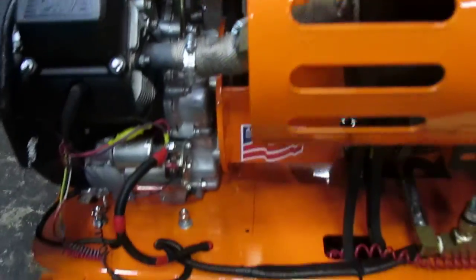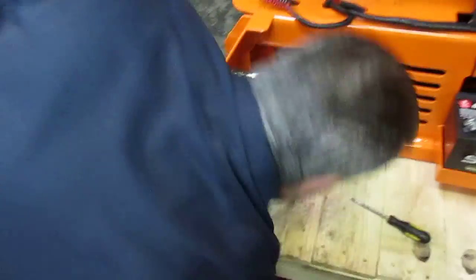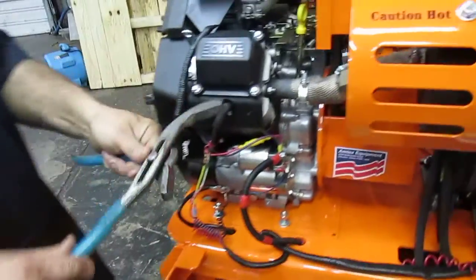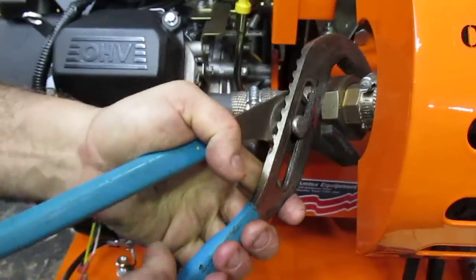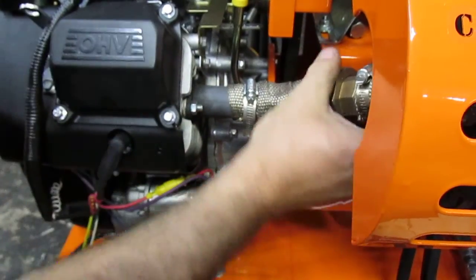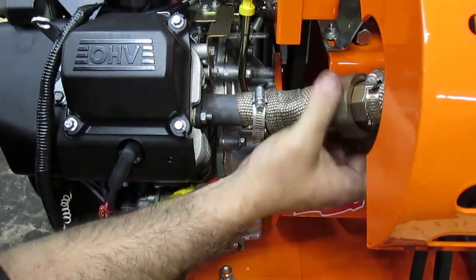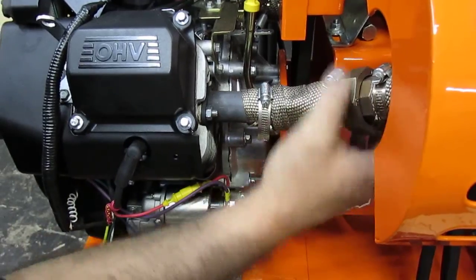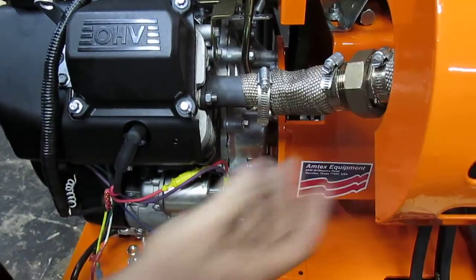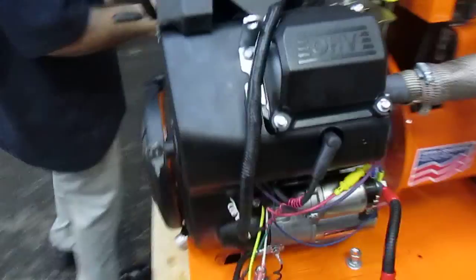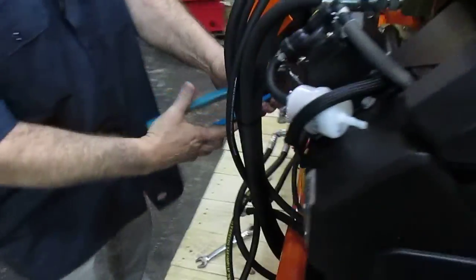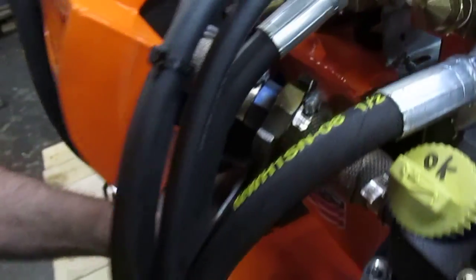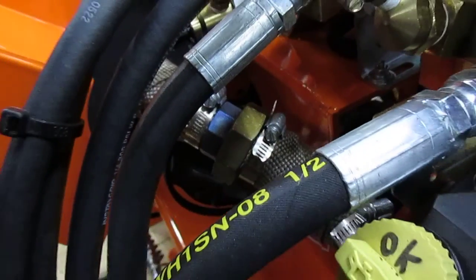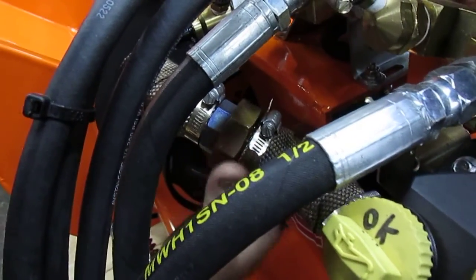The last part is the exhaust manifold. There are two unions. Using a channel lock, simply grab the union and loosen it. These are all done in stainless steel for maximum durability. Coming to the left side of the machine, there's another union. Notice they're not super tight, just snug, because with the heat they do hold on.